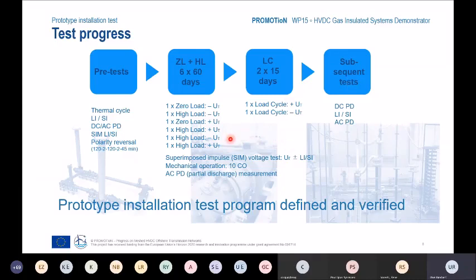DC GIS. From the technical point of view, one major difference between cable test and HVDC test is the superimposed impulse voltage test after each cycle. So we have added a lot of these superimposed impulse voltage tests because that is the most critical test for a DC GIS. Therefore, that was added: one impulse test after each cycle. Of course, we have also added AC PD measurements and DC PD measurements after each cycle.